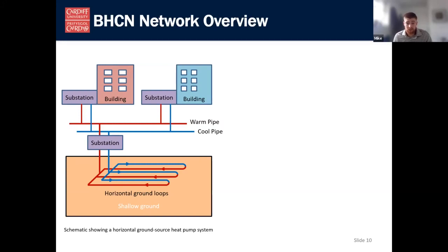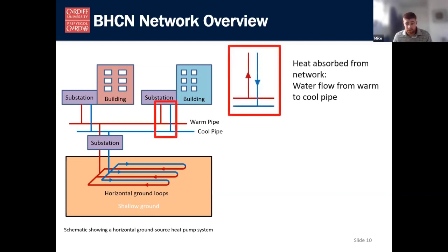So the main thing that differentiates these balanced heating and cooling networks from conventional high temperature district heating is that you have warm and cool pipes rather than supply and return. So the buildings can either absorb heat from or reject heat to the network. And so we have bidirectional mass and energy flows between them.